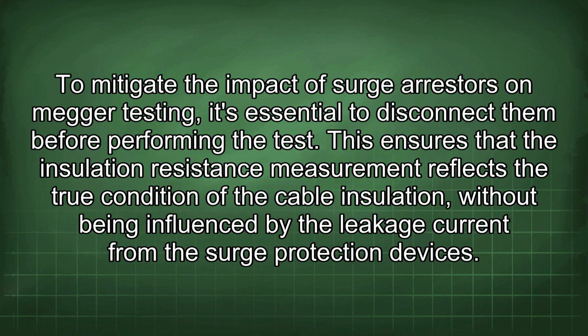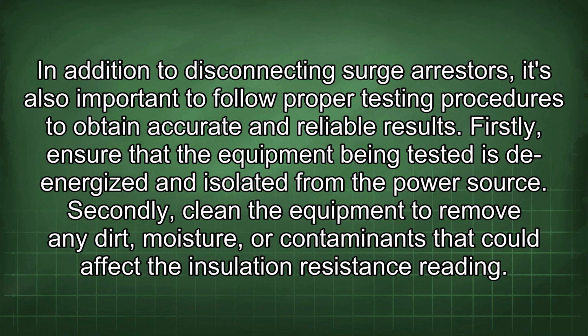To mitigate the impact of surge arrestors on Megger testing, it's essential to disconnect them before performing the test. This ensures that the insulation resistance measurement reflects the true condition of the cable insulation without being influenced by the leakage current from the surge protection devices. In addition to disconnecting surge arrestors, it's also important to follow proper testing procedures to obtain accurate and reliable results. Firstly, ensure that the equipment being tested is de-energized and isolated from the power source. Secondly, clean the equipment to remove any dirt, moisture, or contaminants that could affect the insulation resistance reading.